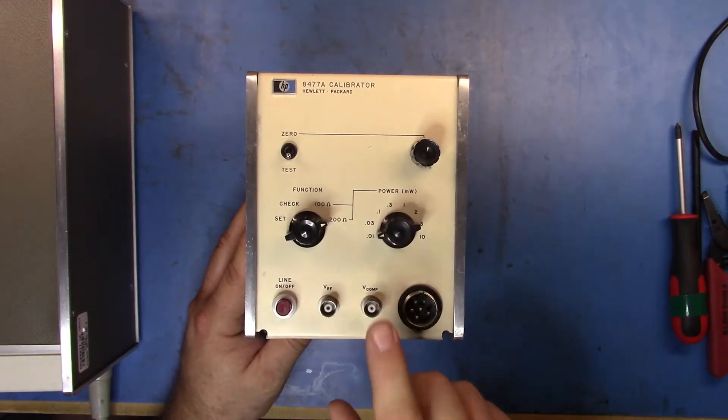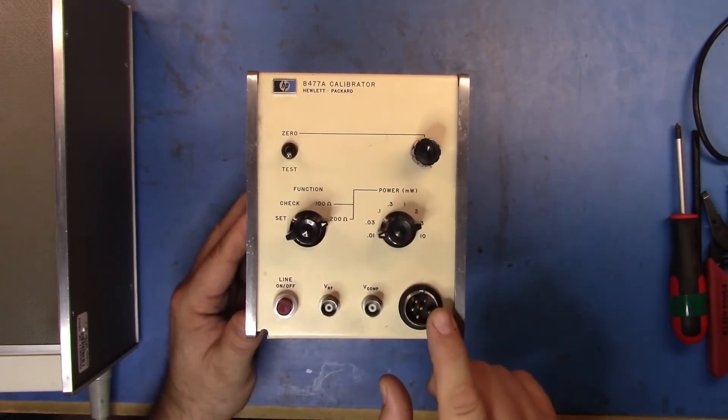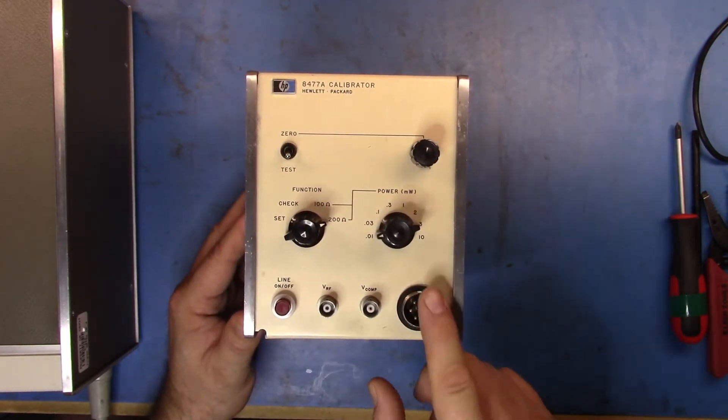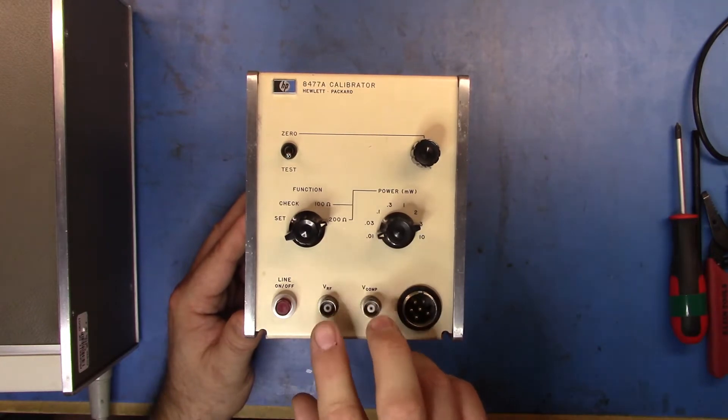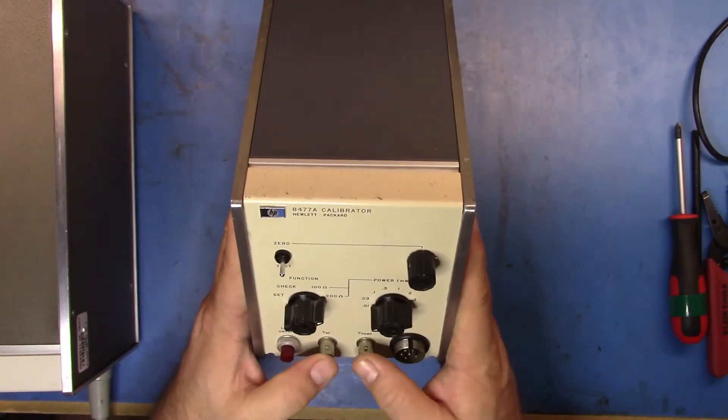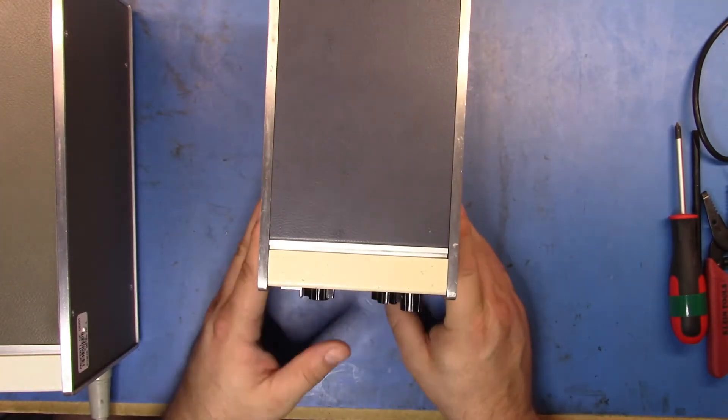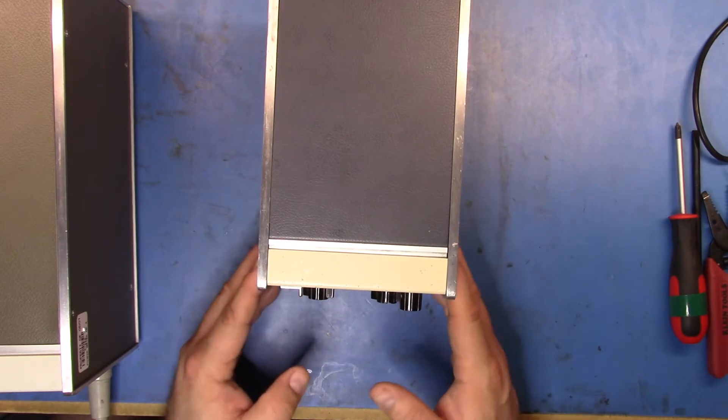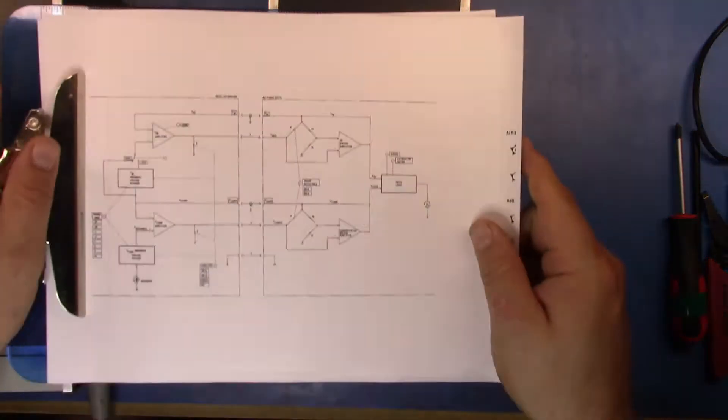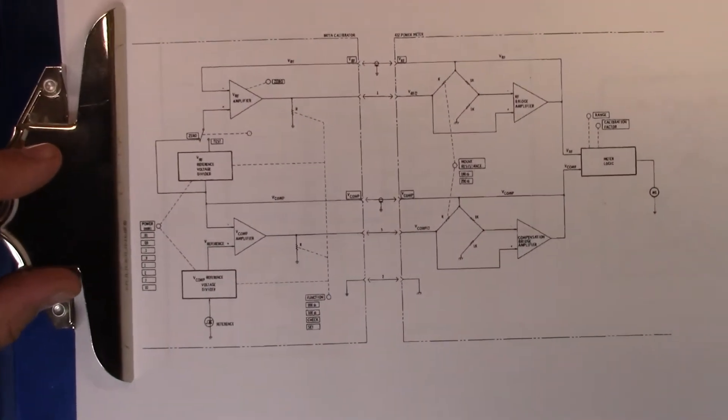Now, how this works is it connects to the meter through the thermistor mount cable, and has two inputs, or two outputs of VRF, or inputs actually for this guy, VRF and VCOMP. And if you've seen the other video, you would have seen how that system works. So let's take a quick look at how that system block diagram looks.